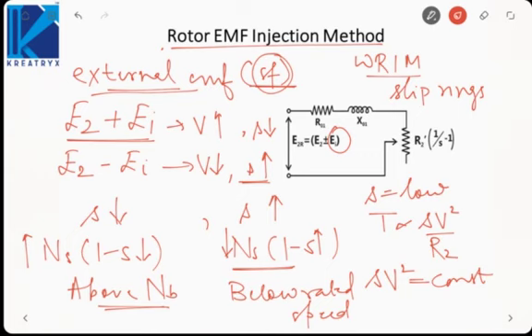To summarize the slip control methods: voltage control decreases voltage so slip increases — below rated speed only. Rotor resistance control increases resistance so slip increases — also below rated speed only. Rotor EMF injection can inject EMF in same or opposite phase, giving both above and below rated speed control of the induction motor.